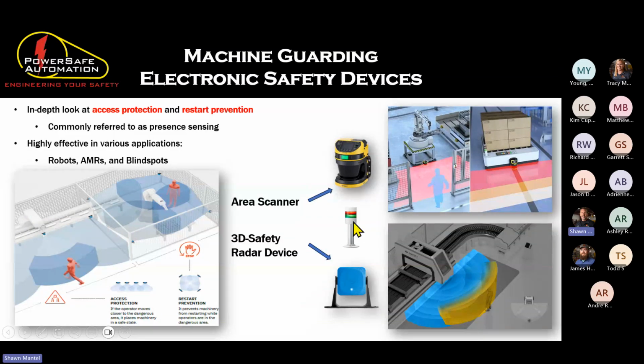And then good practice would be putting stack lights, because these lights are invisible. A lot of times when something is tripped, people don't understand why their machine is tripped, so maybe they'll override it - put it in manual mode and still run it because they don't know why. If they see this light on, then they know one of these devices is tripped.